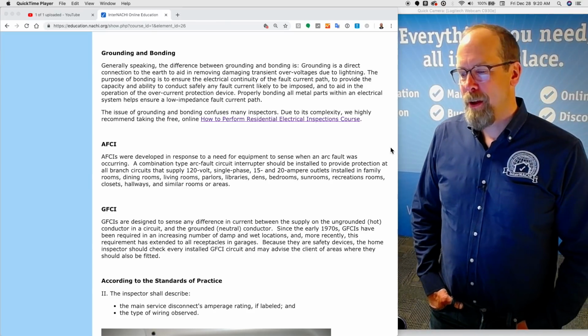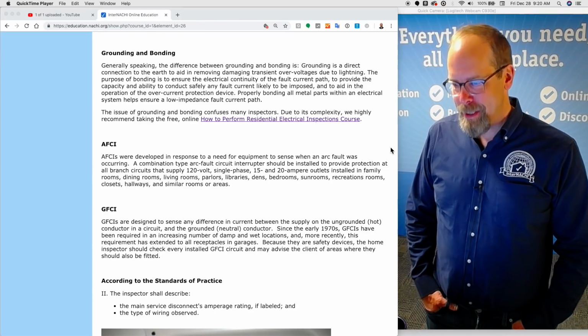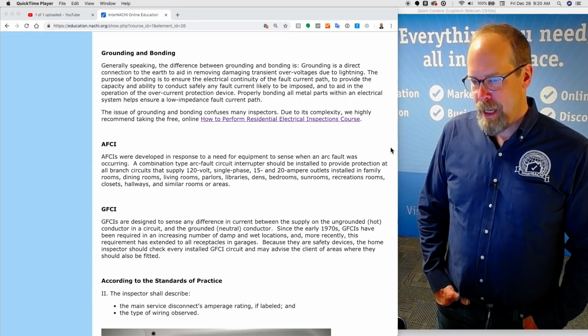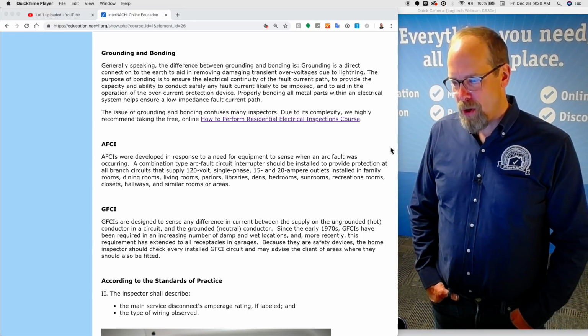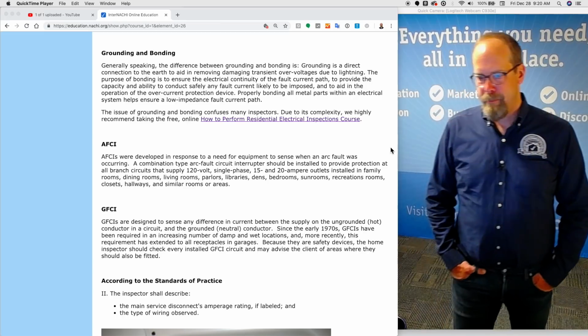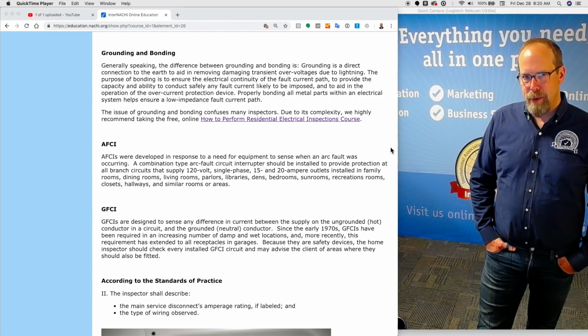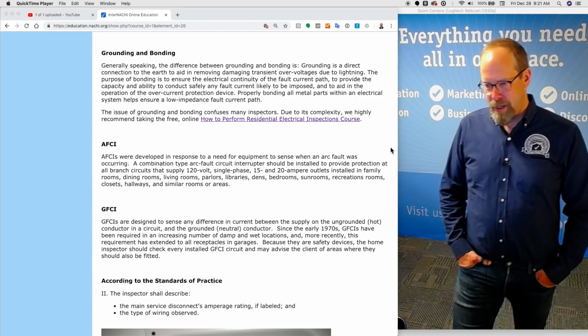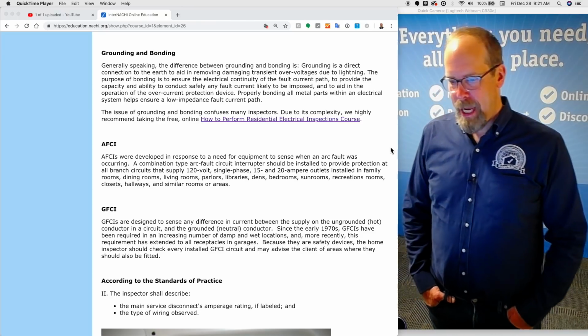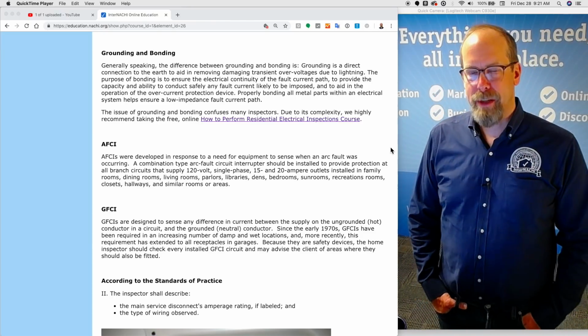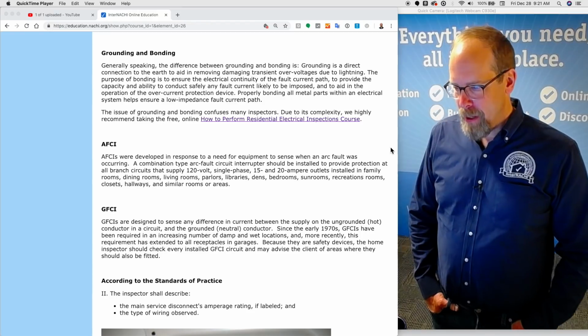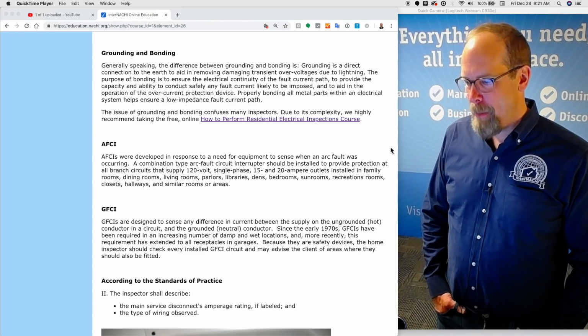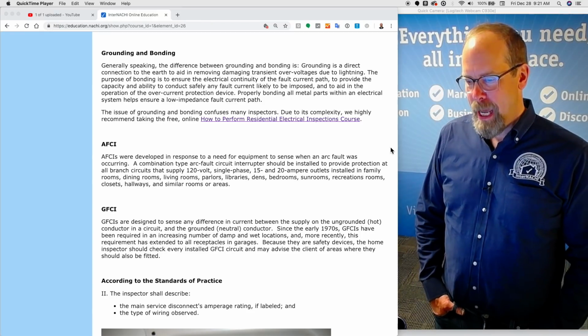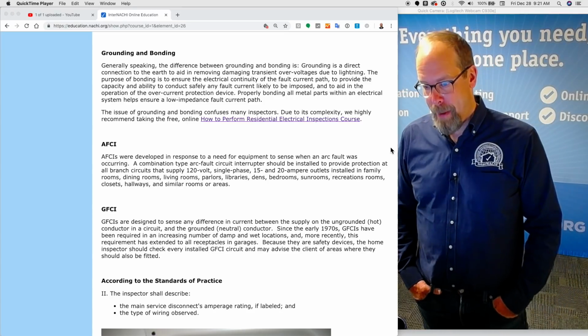Grounding for removing damaging transient overvoltages due to lightning, and bonding to ensure the electrical continuity of the fault current path, and to provide the capacity and ability to conduct safely any fault current likely to be imposed, and to aid in the operation of the overcurrent protection device. Properly bonding all metal parts within an electrical system helps ensure a low impedance fault path.